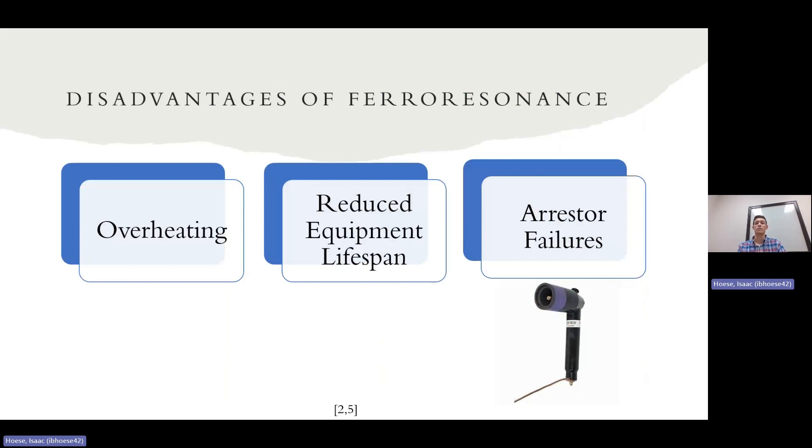And EPRI states, which is the Electric Power Research Institute, states that unchecked voltages can exceed 400% of the nominal line to ground voltage. So it's not just a little bit of over voltage. It's a lot per unit of over voltage that the system can experience.